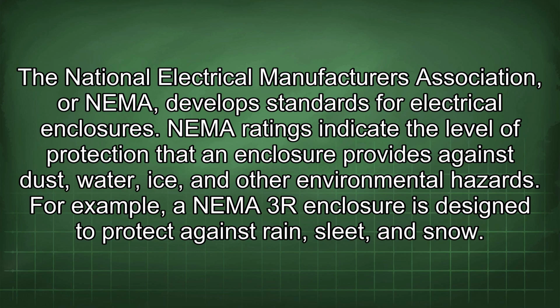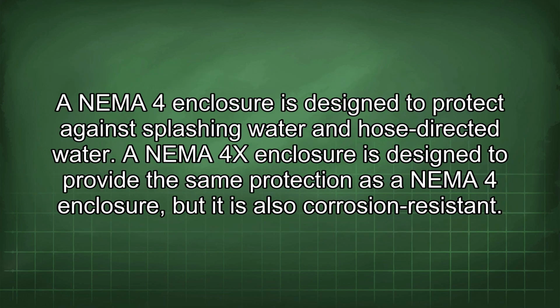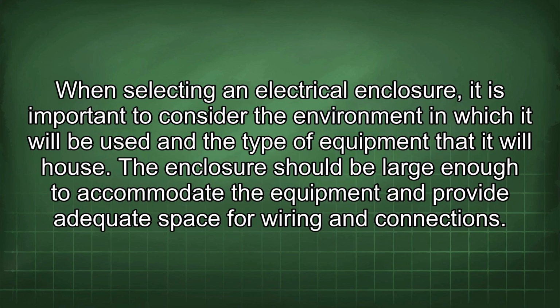For example, a NEMA 3R enclosure is designed to protect against rain, sleet, and snow. A NEMA 4 enclosure is designed to protect against splashing water and hose-directed water. A NEMA 4X enclosure is designed to provide the same protection as a NEMA 4 enclosure, but it is also corrosion resistant. When selecting an electrical enclosure, it is important to consider the environment in which it will be used and the type of equipment that it will house.